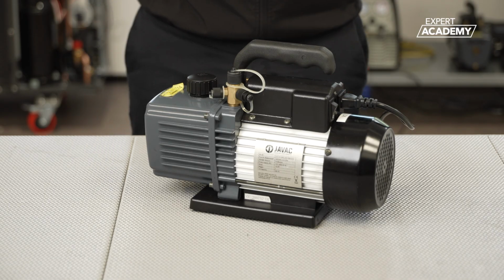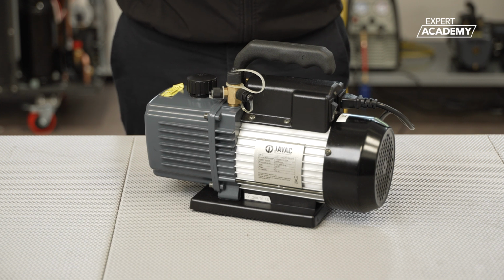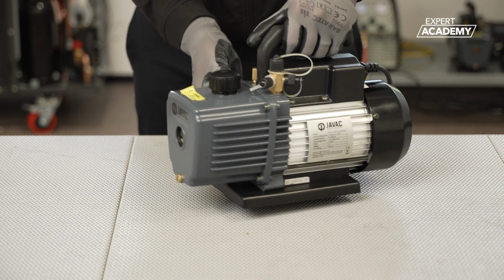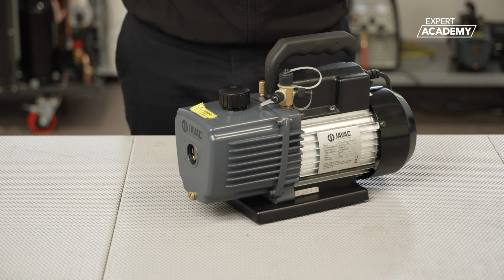Vacuum pumps are used to remove air, moisture and other gases or vapours from a system. Without a vacuum pump, these particles can cause inefficient operation and potential corrosion of internal components. Vacuum pumps draw out moisture and other contaminants from the system circuit, measuring these in microns.